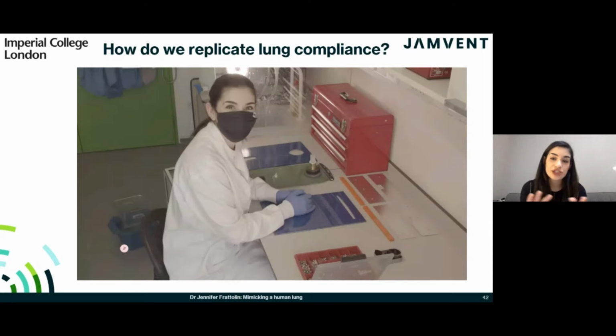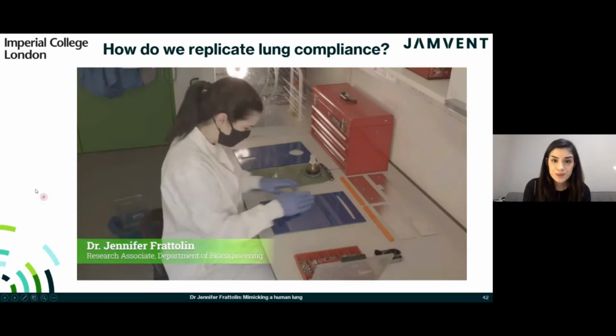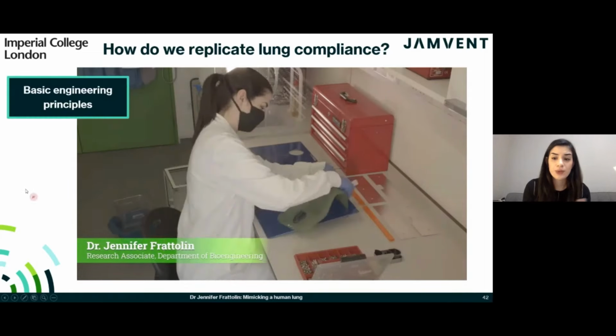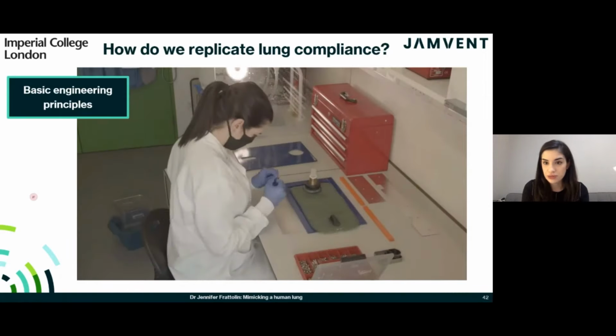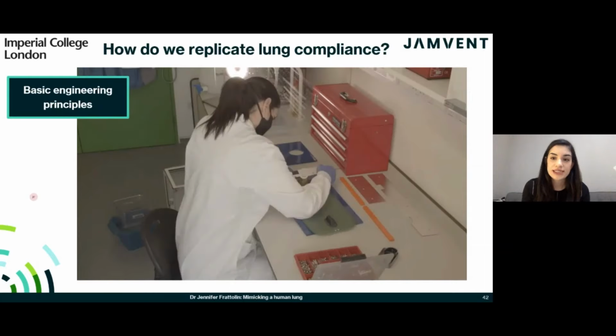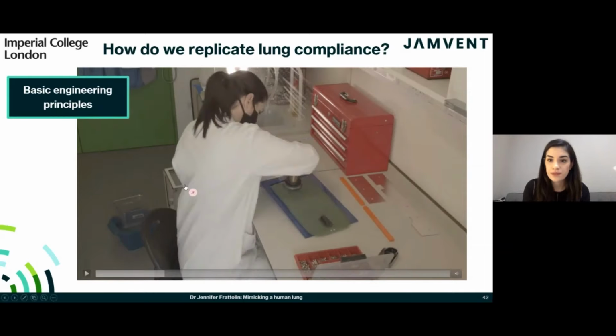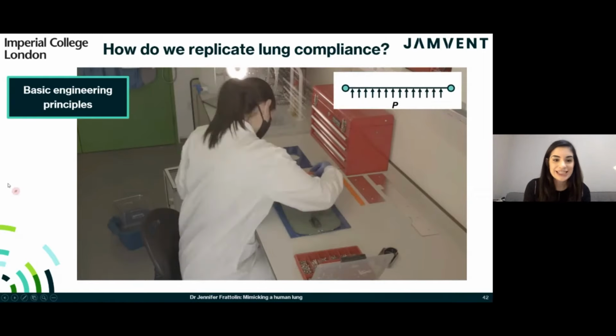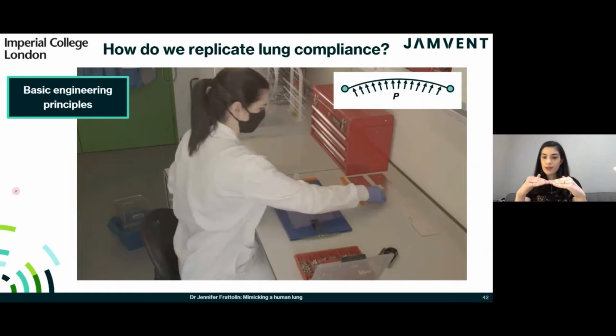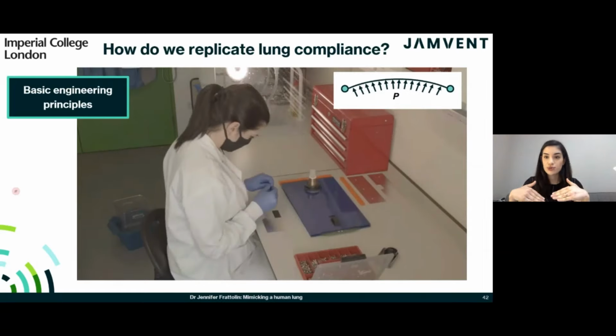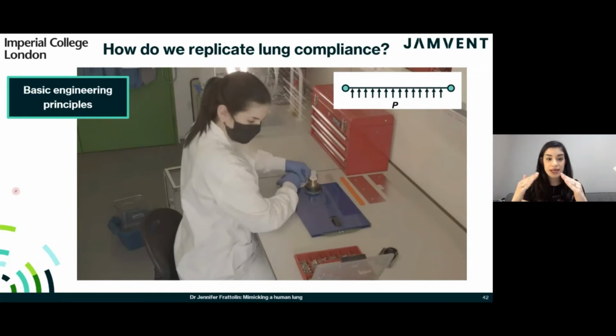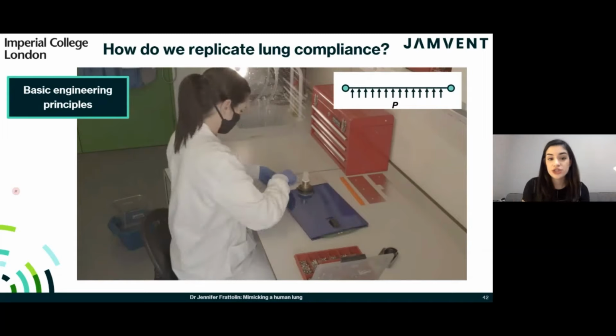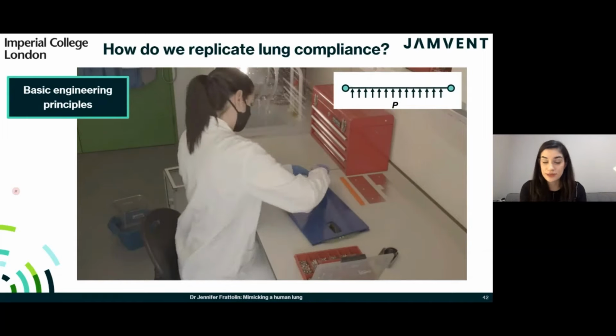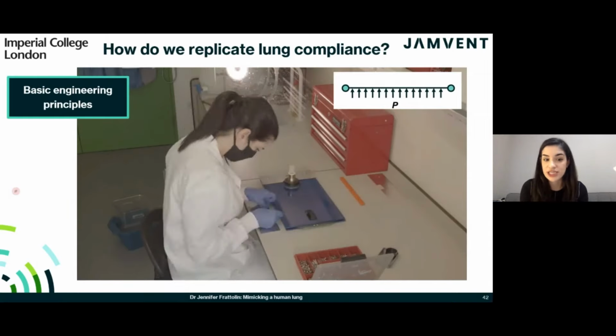So now, how can we build a system that has variable lung compliance in order to take into account disease severity? When we were simulating lung compliance, we really wanted to use basic engineering principles, and so we utilized something called a leaf spring. If you can imagine, a leaf spring is a plastic sheet that's fixed at two ends, and when we apply a pressure to the inside of the sheet, it will begin to bend. The degree to which it bends depends on the overall stiffness of the material. And by changing the stiffness of the material, we can alter the overall compliance of our test lung.